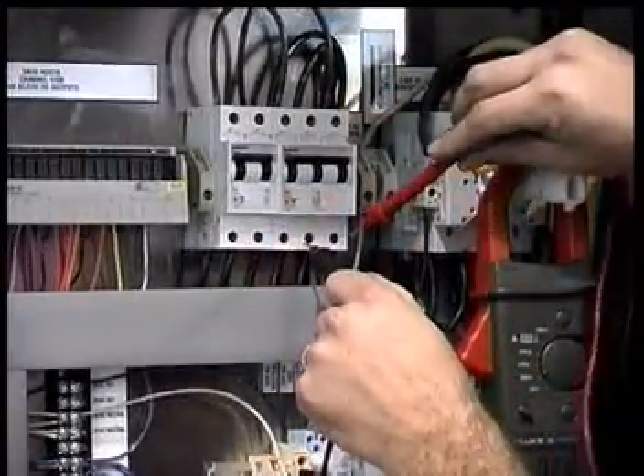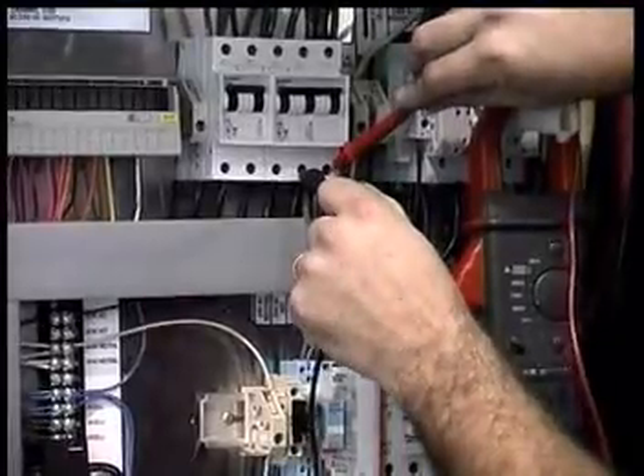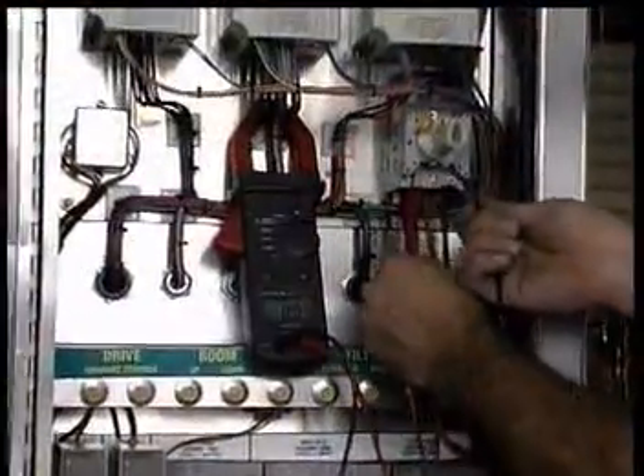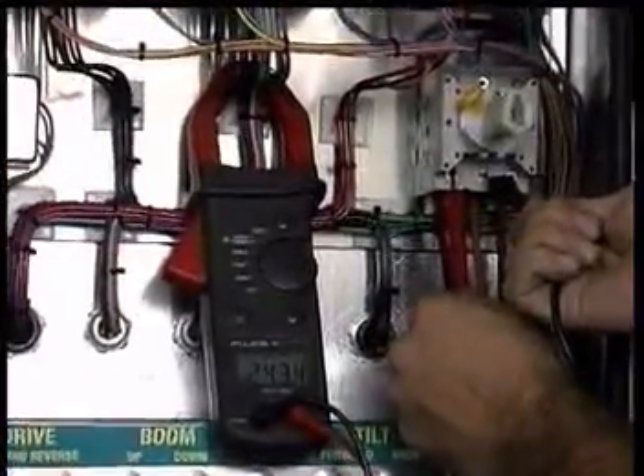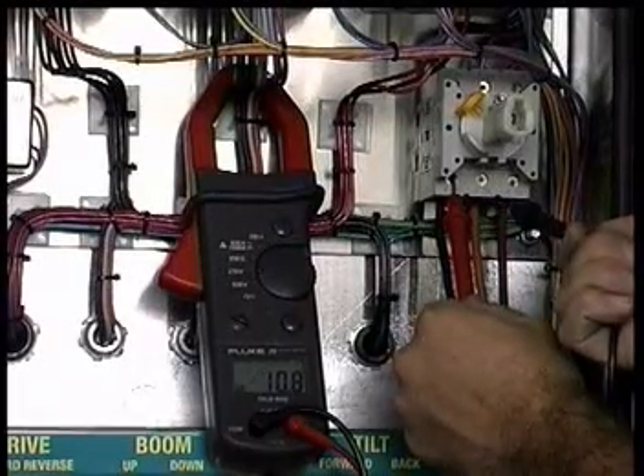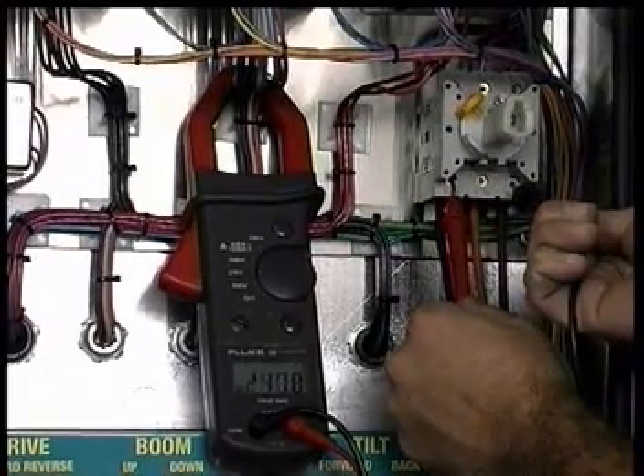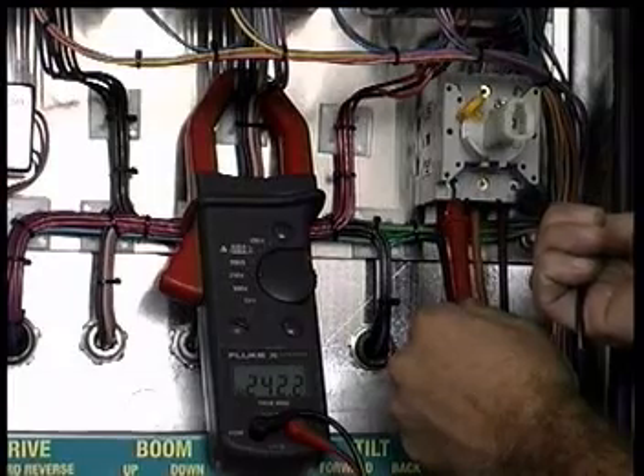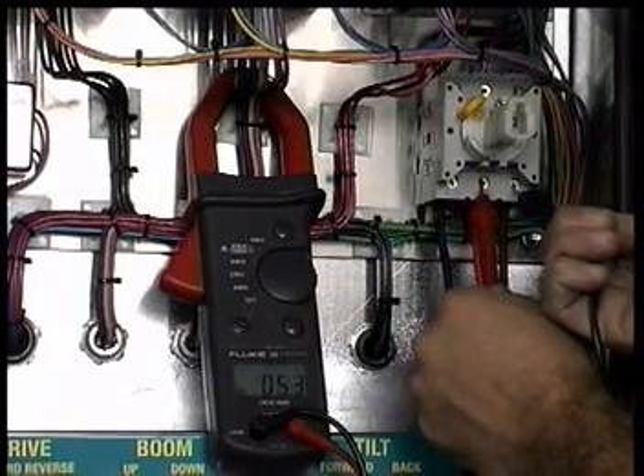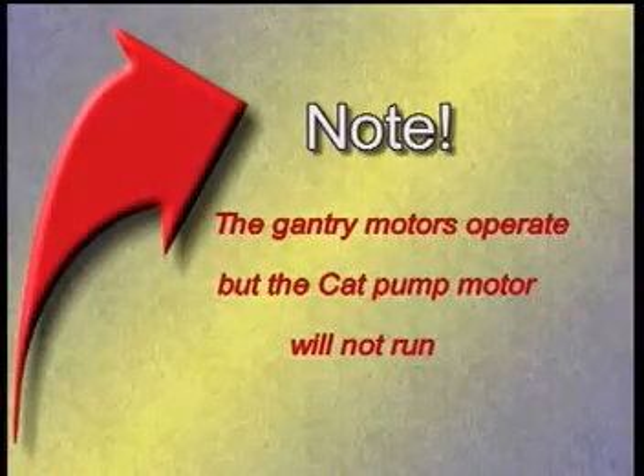If power is present on both sides, we now need to check power at the gantry. In the gantry control panel, check for 220 power at the top side of the gantry disconnect switch and then repeat the process on the bottom side. If there is still no power, the problem is likely in the 12/5 SO cord.